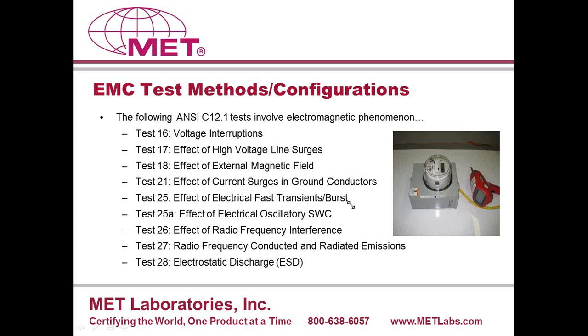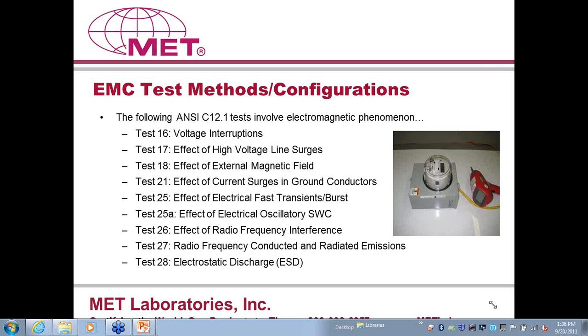The next test is test number 18, effect of external magnetic field. When there is a strong external magnetic field on a current transformer or a pulse transformer, the transformer will saturate, and the output will be less than proportional to the input being applied. This will obviously result in a revenue loss to the utility company. The intent here is to subject the metering device to an external field and then monitor the change in the performance.